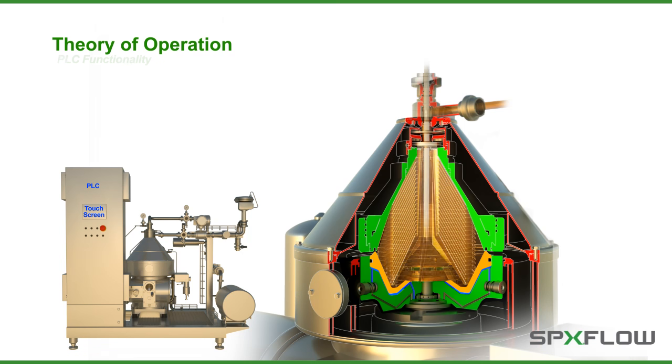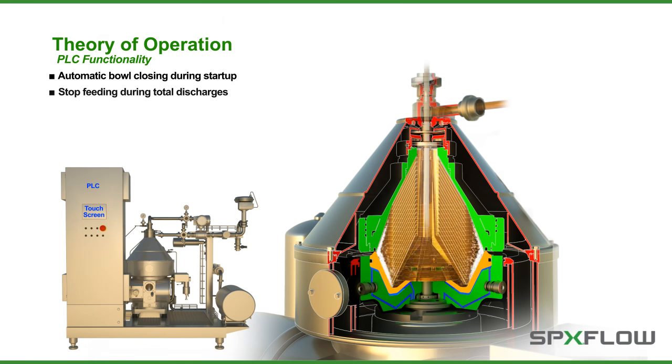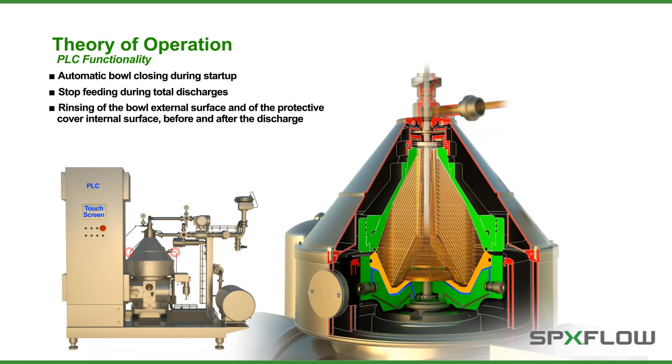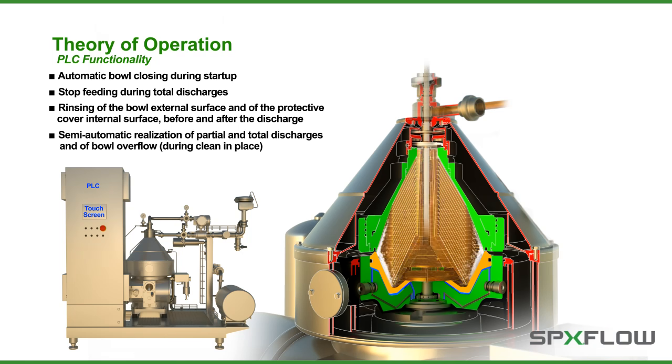The PLC can also perform the following functions: automatic bowl closing during startup, stop feeding during total discharges, rinsing of the bowl's external and protective internal surface before and after the discharge, and semi-automatic realization of partial and total discharges and of bowl overflow during clean-in-place.